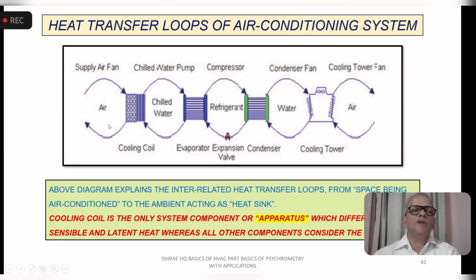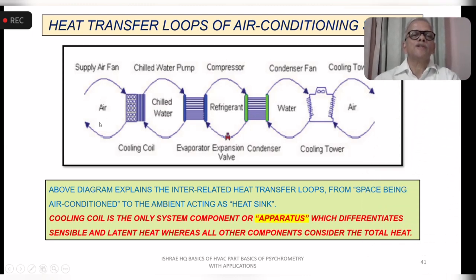The first loop you see is the air, which is your conditioned space. You have a supply fan circulating the air, which passes over the coil, getting cooled and dehumidified, and is pumped back to the space, again picking up heat and going back. So that is your supply fan. After the cooling coil, you have a chilled water loop, a refrigeration loop, then the condenser, then the heat removal back to there. So the above diagram explains the interrelated heat transfer loops from the space being air conditioned to the ambient, which is the heat sink.